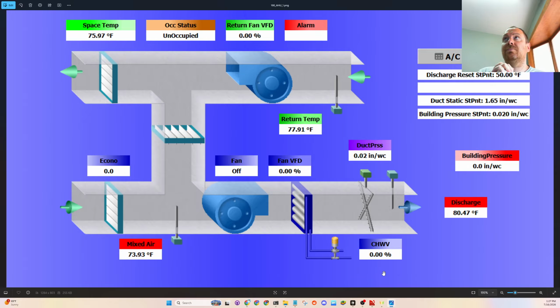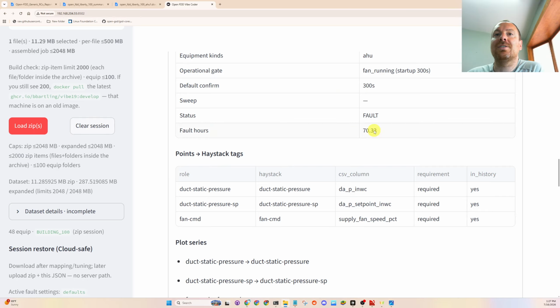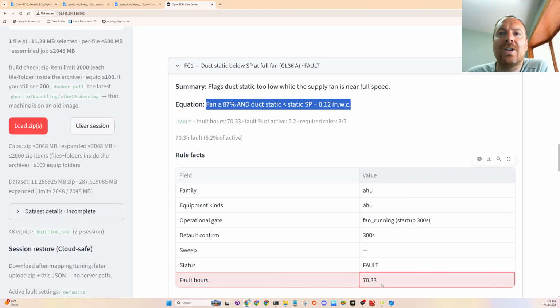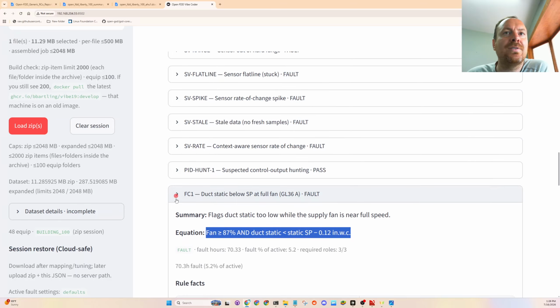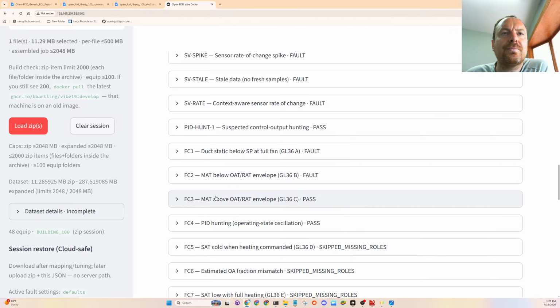And I think what's happening is they're not interlocked, and that's what's causing this. This is just a hunch, that the chiller shuts down on its own operating schedule and it's not looking to see if the air handling unit is still running or calling for cooling. This is a hunch. So we have 70 hours, which could be directly inputted into some kind of equation for energy savings. I'm not paying too much attention to this mixed air temp below outside air and return air. I kind of wanted to zero in on this.